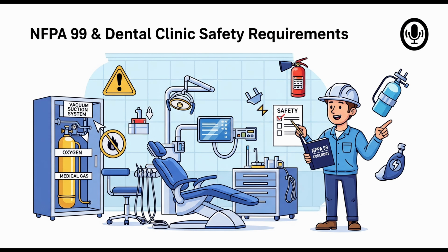Yes, there's a point about grounding. Section 6.3.2.2.5 discusses special isolated ground receptacles, sometimes used for sensitive electronics. However, subsection B explicitly states these shall not be installed within a patient care vicinity. Why not? In patient care areas, the priority is maximizing electrical safety for the patient, often through multiple redundant ground paths. Isolated grounding compromises some of that redundancy for the sake of cleaner power. So, standard, reliably grounded outlets are the rule near the patient.